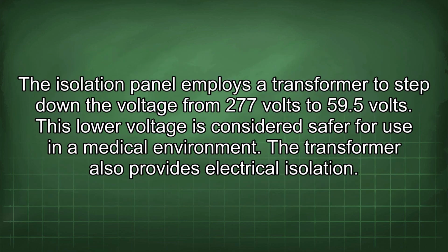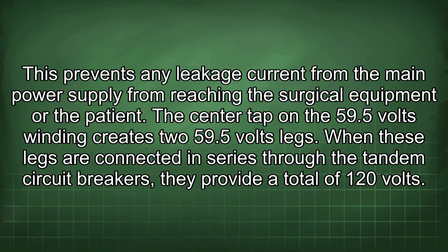The isolation panel employs a transformer to step down the voltage from 277 volts to 59.5 volts. This lower voltage is considered safer for use in a medical environment. The transformer also provides electrical isolation. This prevents any leakage current from the main power supply from reaching the surgical equipment or the patient.